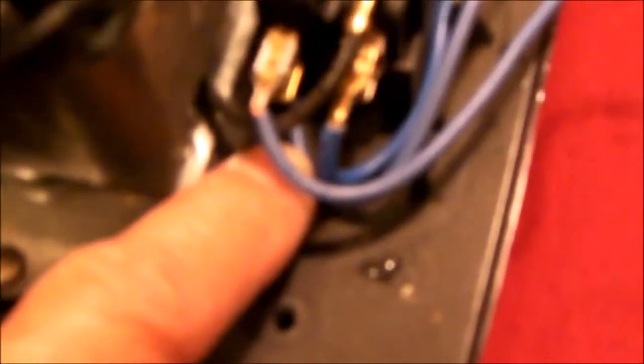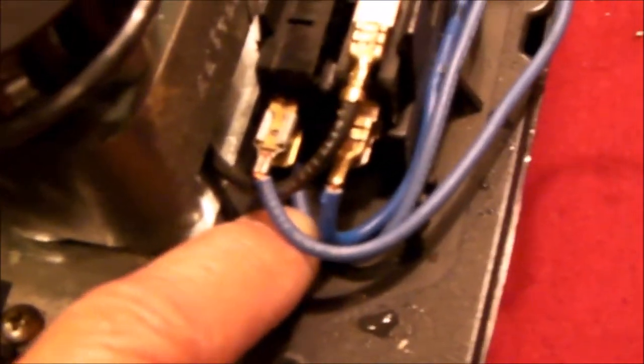When the pump is shipped from the factory, the wires are connected to the common, which is on this switch on the left. In this particular configuration, it's the bottom-most terminal. If you pull the switch out, you'll see the markings on it: common. And the other wire is connected to the normally closed contact.